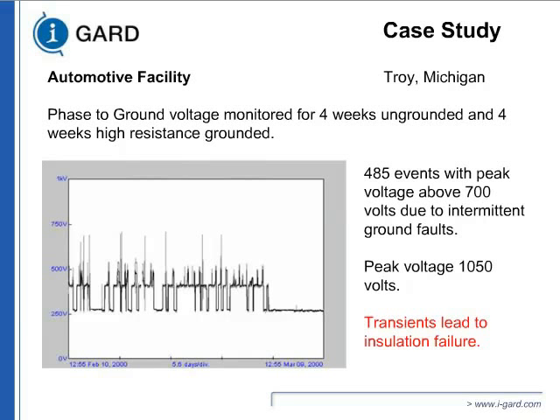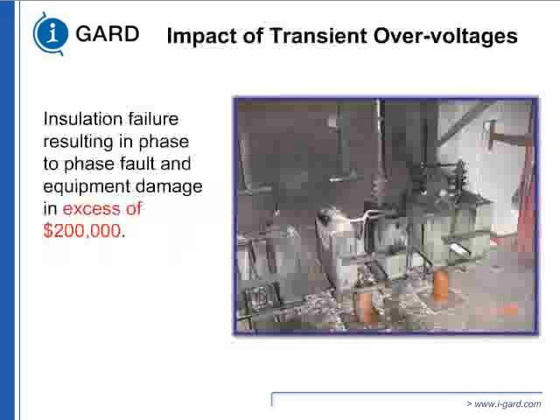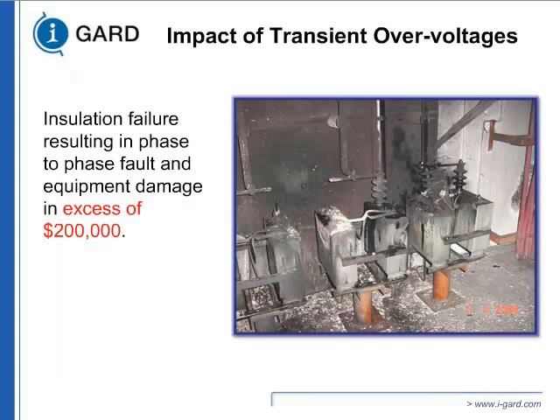This is the one fault, that insulation failure, that resulted in equipment damage in excess of $200,000. And the bad part about delta intermittent voltage is you don't know which part of the equipment will be damaged. For example, on solid grounded, you know where the fault is; only that equipment is affected. On an ungrounded delta system, you don't know which part is affected. All of them may be taking an overvoltage.